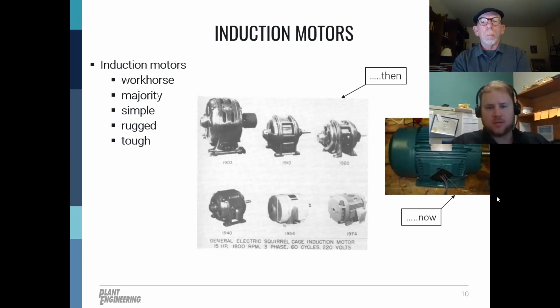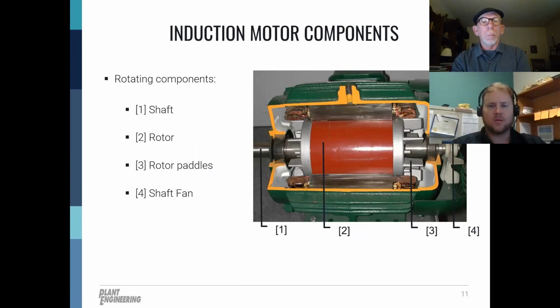And now I'd like to go over a few of the basic components that you might find in an induction motor. You'll hear some of these components referenced throughout the rest of the presentation today. So this first slide is going to be rotating components. The rotating components include the shaft, which is going to be on the left. That's where the motor will couple up to the load, whatever the load may be: pump, fan, blower, elevator, whatever kind of conveyor belt application. The rotor, which here is painted red, and then the rotor paddles and balancing nubs shown in the picture are cast aluminum. And then lastly, labeled number 4 on the slide is the shaft fan, which here is plastic. The side of the motor that couples to the load is called the drive-end, and the other side is simply called the non-drive-end or the opposite drive-end. Keep it very simple.